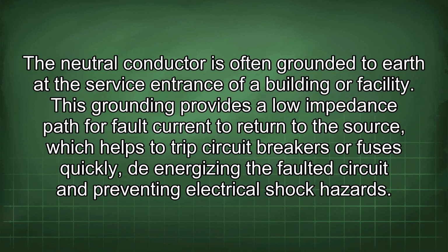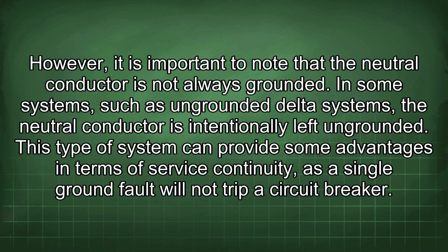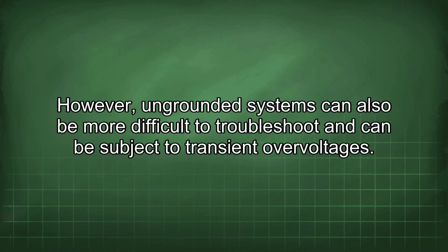The neutral conductor is often grounded to earth at the service entrance of a building or facility. This grounding provides a low impedance path for fault current to return to the source, which helps to trip circuit breakers or fuses quickly, de-energizing the faulted circuits and preventing electrical shock hazards. However, it is important to note that the neutral conductor is not always grounded. In some systems, such as ungrounded delta systems, the neutral conductor is intentionally left ungrounded. This type of system can provide some advantages in terms of service continuity, as a single ground fault will not trip a circuit breaker. However, ungrounded systems can also be more difficult to troubleshoot and can be subject to transient overvoltages.